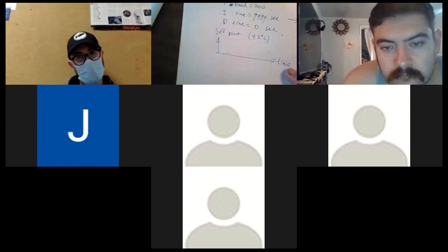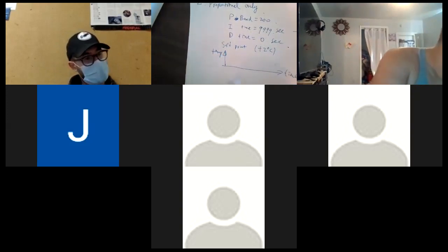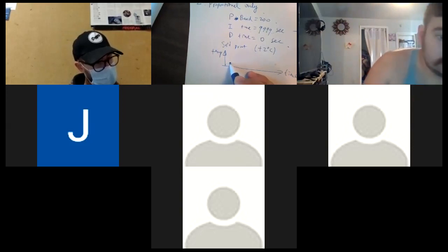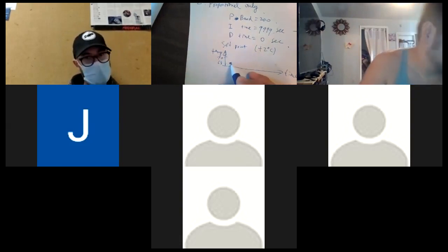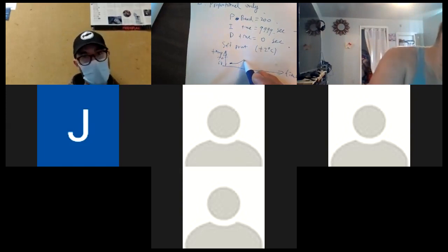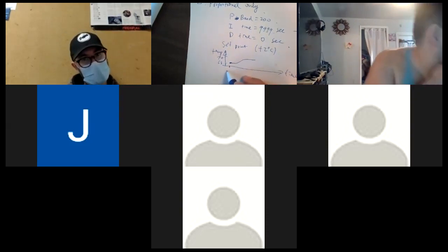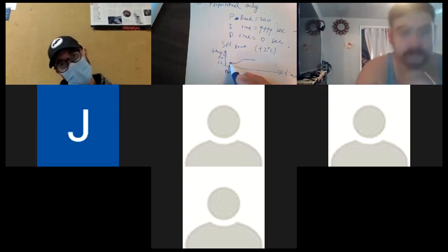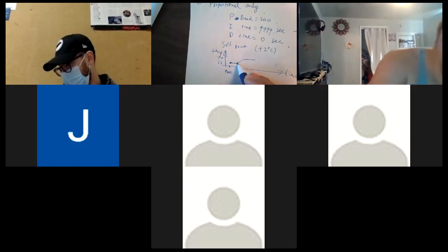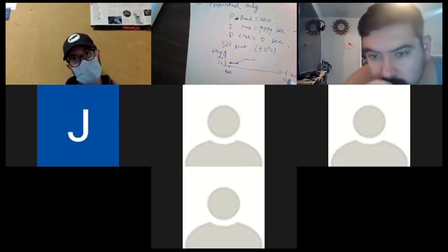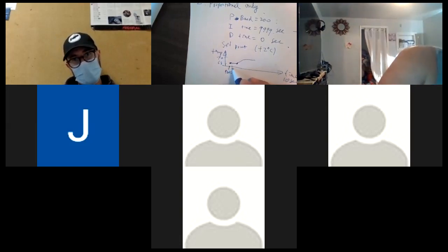Horizontal will be time, vertical will be temperature. This is where I start, 68 degrees, and this is where I want to end, 70 degrees. You notice that your controller will do something like this. That's where you turn on. You start here, and it has a long delay. You will record your temperature, for example, every 10 seconds. You write it down with a pen, and then you plot it: 0 seconds, 10 seconds, 20 seconds. Mine is very slow, so the delay is quite significant. After about 1 minute of delay, 60 seconds, the temperature starts to rise.